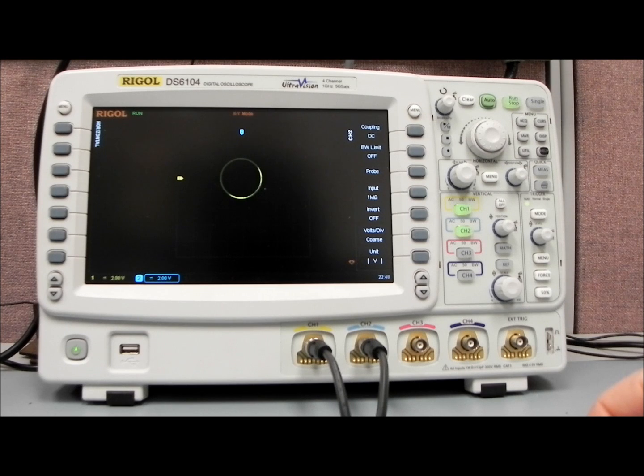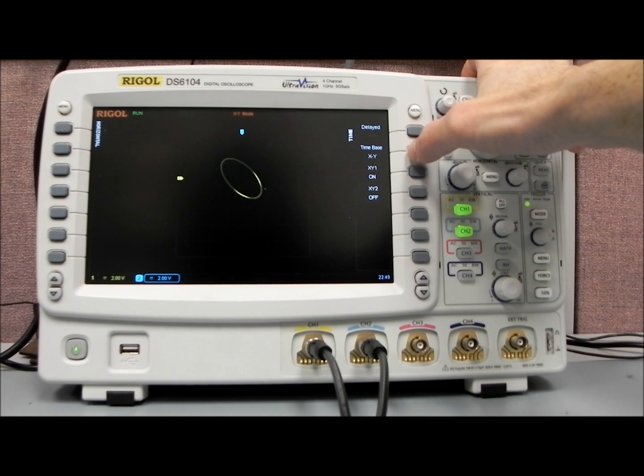If we did something like 125 degrees out of phase, you'll see that will turn into an ellipse. So that can be very useful when you want to see the phase differential between two incoming signals. Again, that's the X versus Y mode.